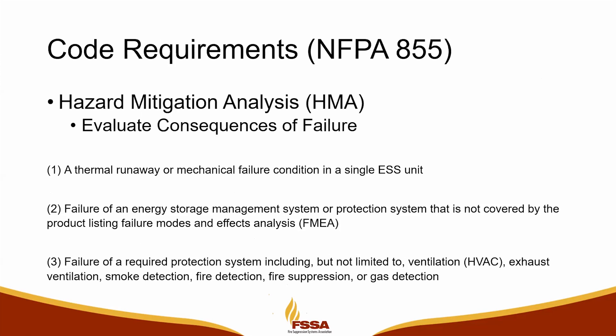Hazard mitigation analysis — the HMA — this is step number one. This is the first thing that you as manufacturers, installers, or property managers need to talk about: do we have an HMA for our batteries? If you don't know the technology when picking a site, you normally have a couple in mind, so make an HMA with all three technologies and get rid of the ones you don't end up using.